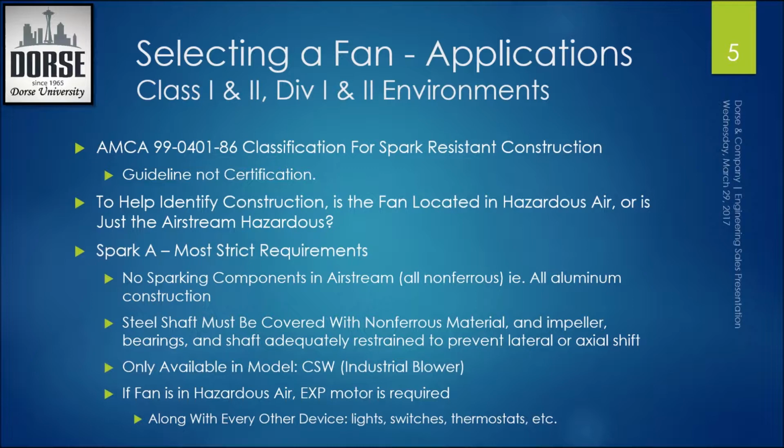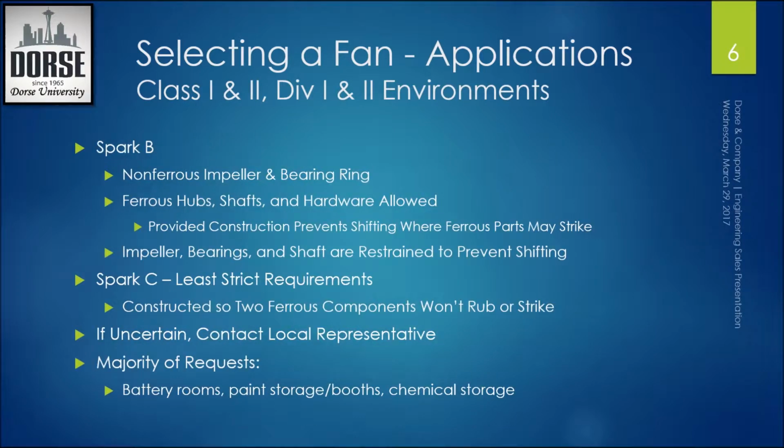But one thing to note is sometimes we jump to Spark A and it might not be necessary. So it's something to think about. Are other devices in this space also rated for Spark A or explosion proof? You know, are the lights and switches and thermostats all rated for that type of environment? It's not always the case. Something to think about. Maybe it's not necessary to go to Spark A.